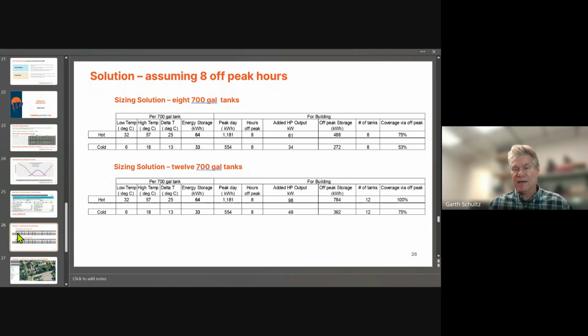The way this is set up is you have air source heat pumps on the outside charging the tanks. The tanks are in a twin pipe configuration into the church, and inside the church we have liquid to air heat pumps that, if required, can turn on to boost the temperature up to final delivery. But most of the time they're just acting as radiators into the system. So it's a good interplay on how to satisfy electrification of heat and use thermal storage for best benefit to the customer.